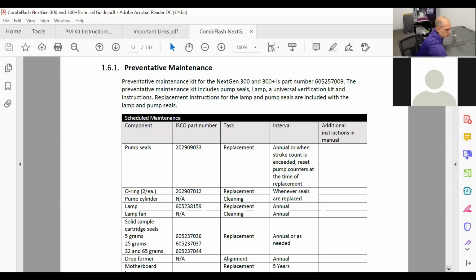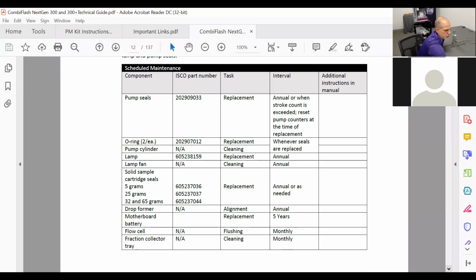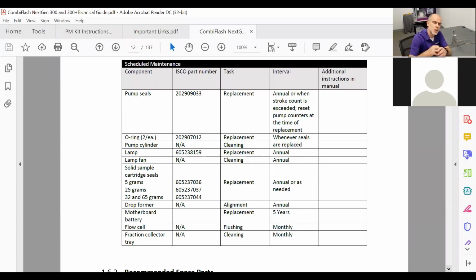All right, so if you've got solid sample cartridges, and these are metal devices that go onto the cartridges. Cartridges are typically used for solid sample, even though I have seen some used for liquid, but there are seals on these solid load cartridge caps. And one thing you'll start to notice is when you use a cartridge with a sample in it and you move the plunger down, you're going to see liquid level going above where that seal is. And it's a big white Teflon seal. You can't miss it. Now, if that liquid's going above and beyond where that seal is, it's time to replace it. And the good news is that's much cheaper than replacing your whole cartridge cap. So we've got part numbers here on this table for you.